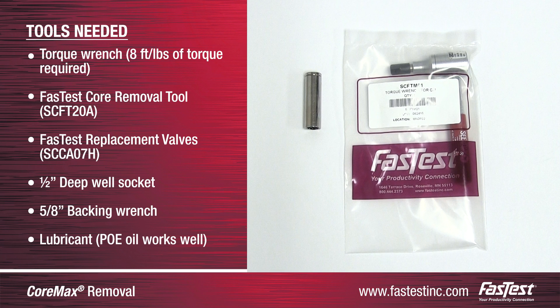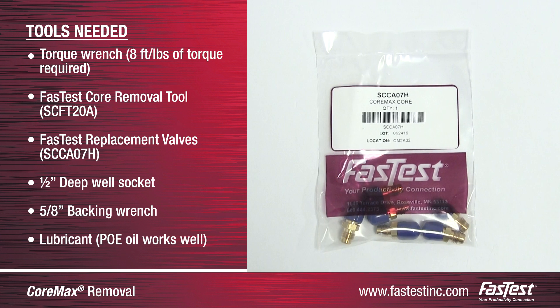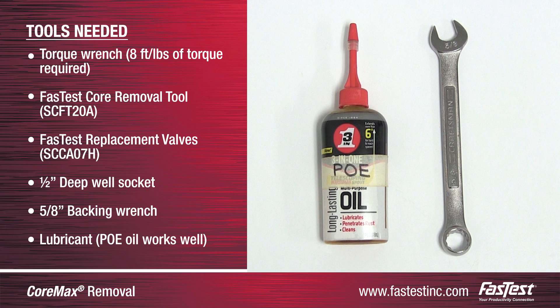A torque wrench — eight foot-pounds of torque will be required — a FasTest core removal tool with part number SCFT20A, FasTest replacement valves with part number SCCA07H, a half-inch deep well socket, a 5/8" backing wrench, and lubricant. FasTest recommends a POE, or polyester oil, or compressor compatible oil.